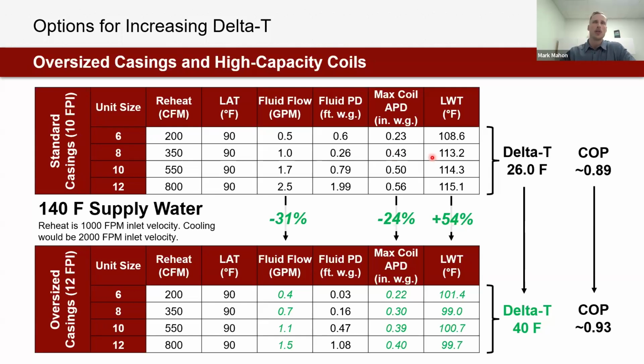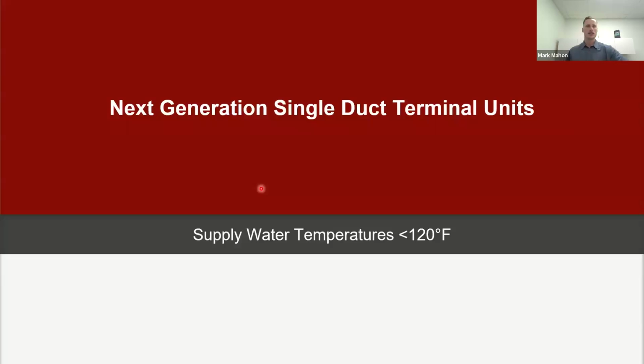The real reason why I like to pull this up is this is the best case scenario coil configuration we currently have in market, historically have had in market, for low hot water supply temps. And so at 140, this is a beast of a box. It has plenty of heat available to us. And I like to call out, when we pair oversized casings and high capacity coils, we actually still get a reduction in air pressure drop. The effective surface area increase is greater than the added resistance to airflow we see from the increased fins per inch here. So in this case, a large delta T of 40, good boiler COP, this is a beast of a box for 140-degree supply water temperatures. But the question would be, what if it's lower?